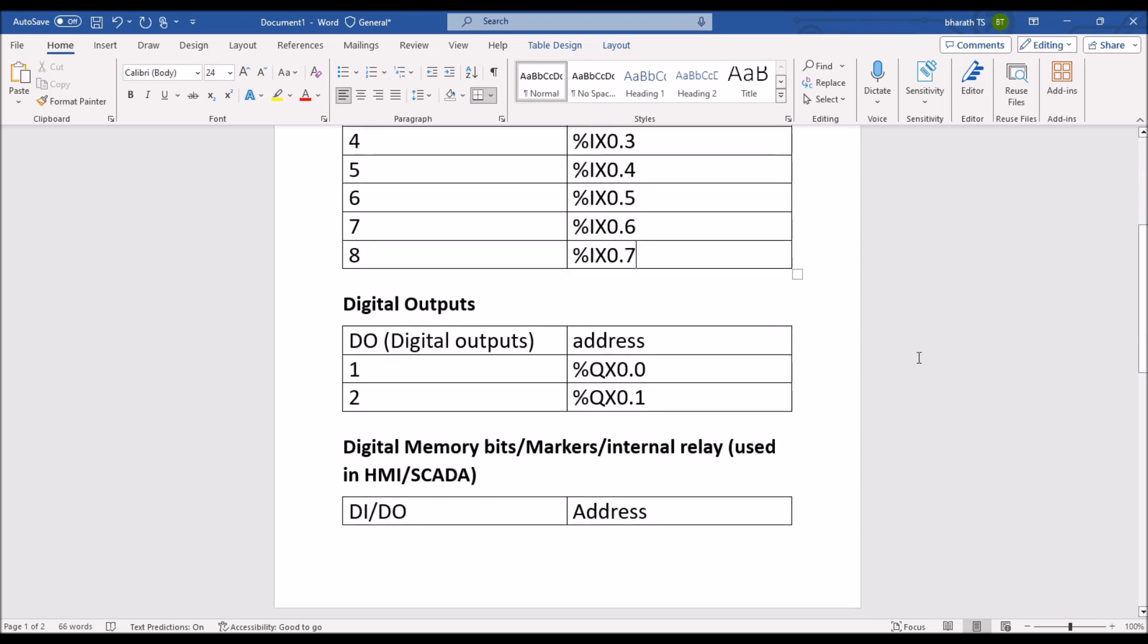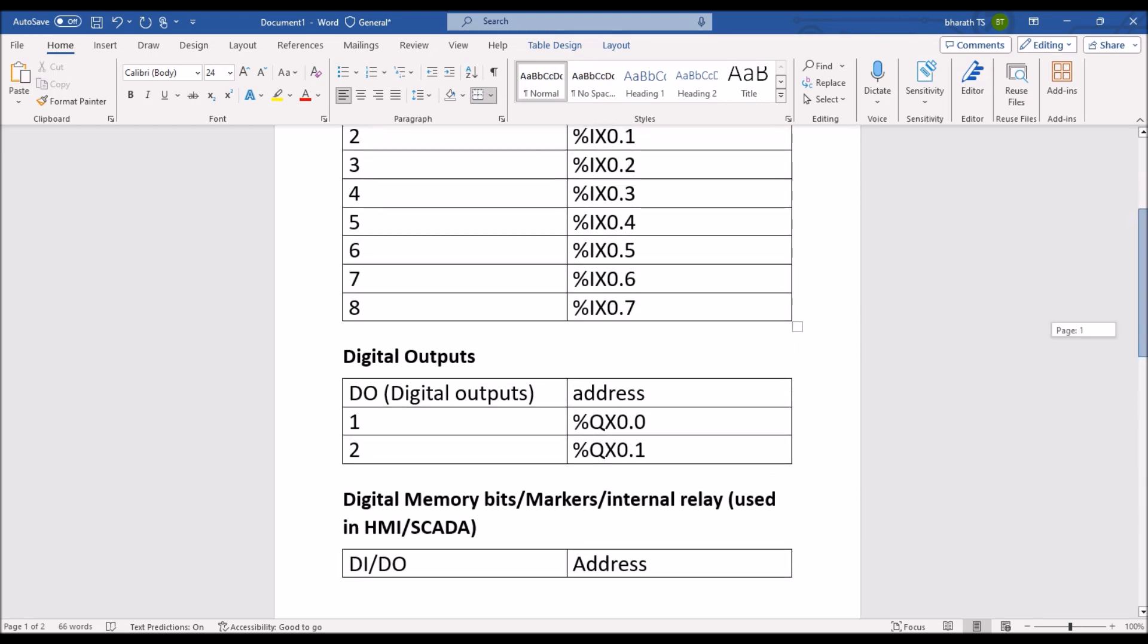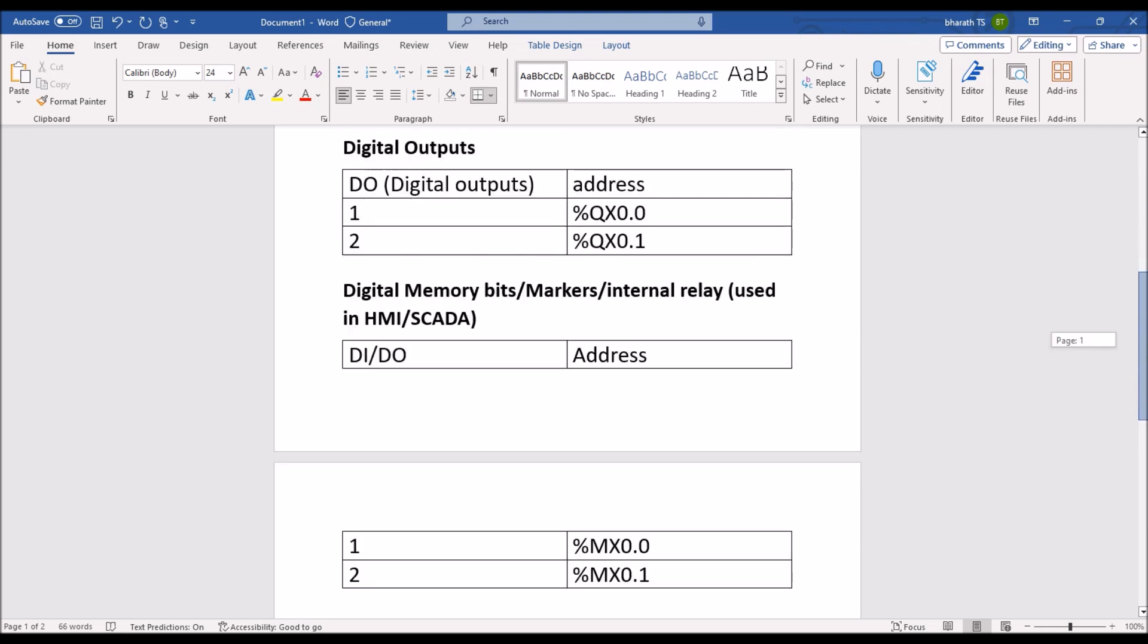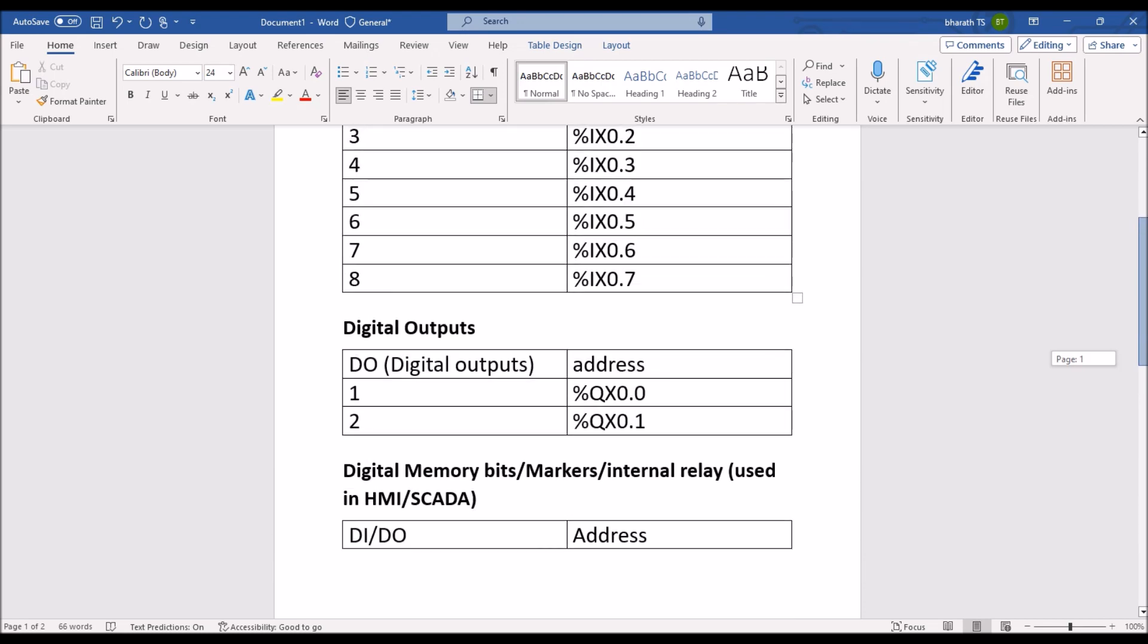Like that output is also 8 outputs or 24 inputs. So this is how we can do the address. If one byte is over you can go to second byte, second byte can start from 1.0, so 1.0 to 1.7. QX0.0 that is the syntax for output. Memory bits syntax is percentage MX0.0, memory is nothing but internal relay, generally it is used in internal variables, it is used in HMI and SCADA programming.